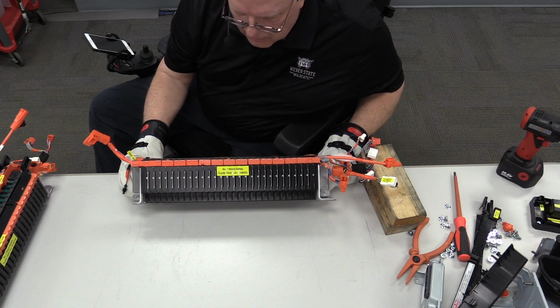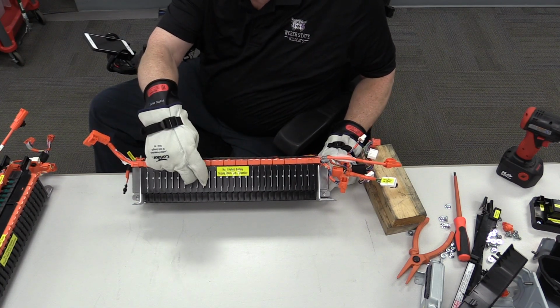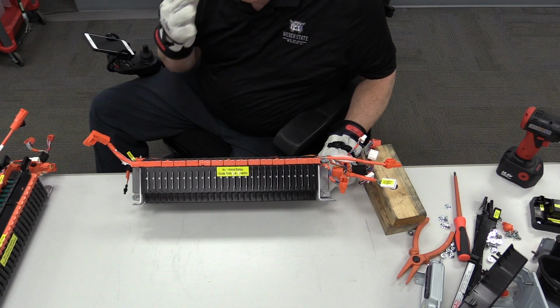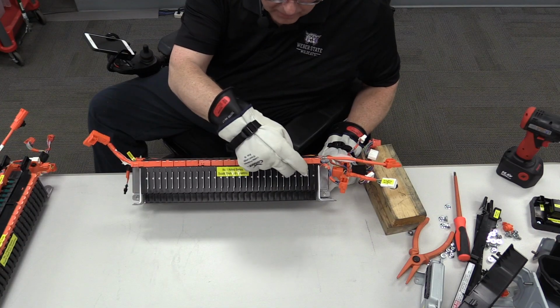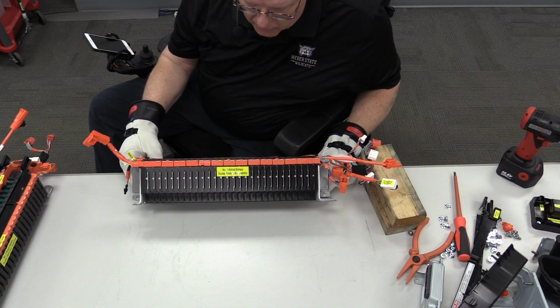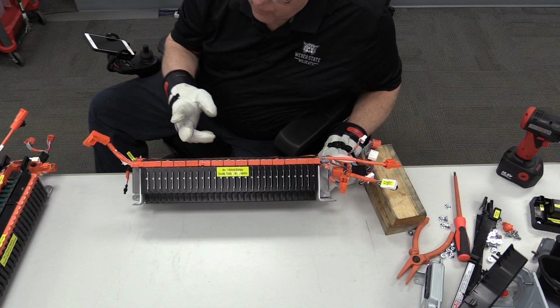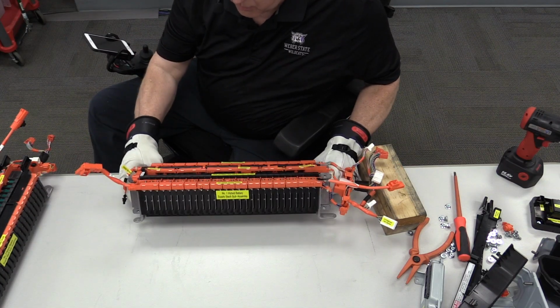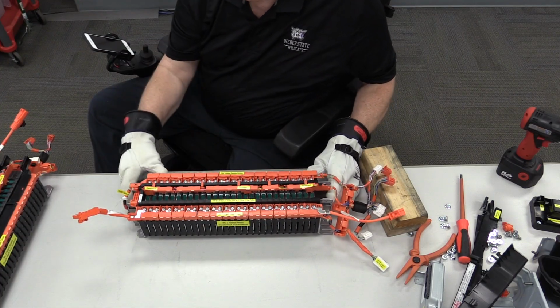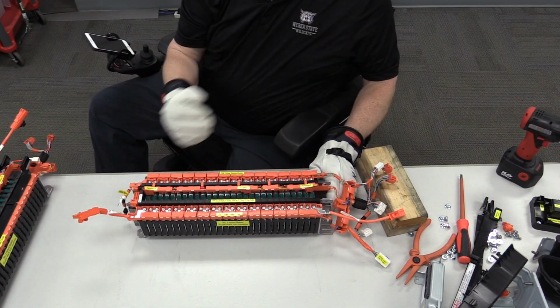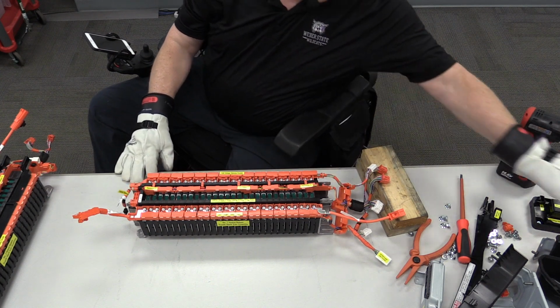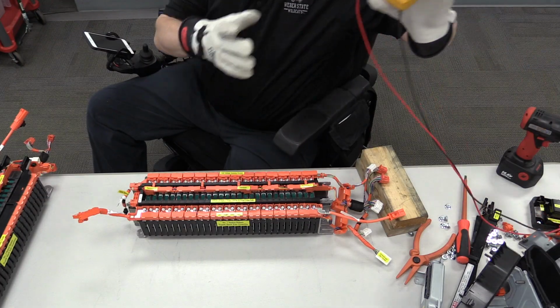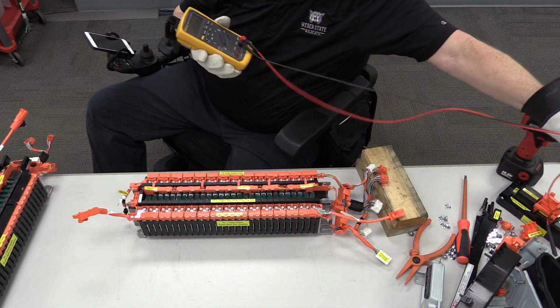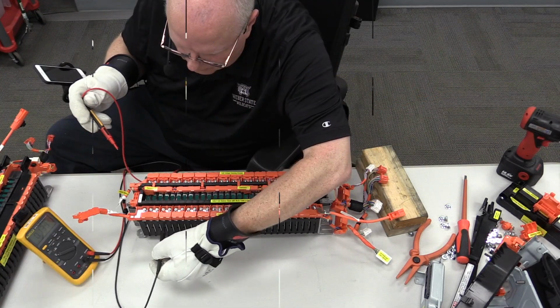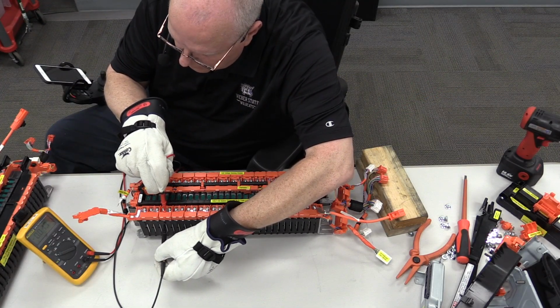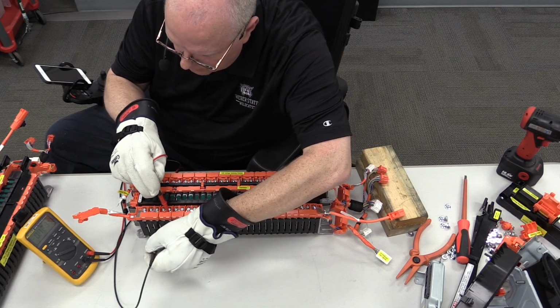I know on some lithium-ion batteries they tell you not to touch the sides of the batteries because some of the sides are conductive. I don't know if that's the case here on these. I guess I can put a multimeter on it and see. I believe these are there to block the air from coming out the side of the batteries and force it to come up the front or the top of the batteries and go out through that ducting on the side. Let me grab my multimeter and let's see if those sides are conductive. Okay, so we'll pick a cell, go right here, nothing, nothing.